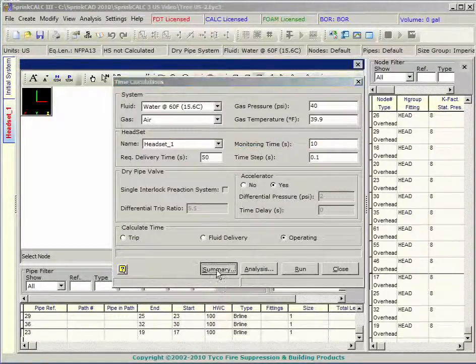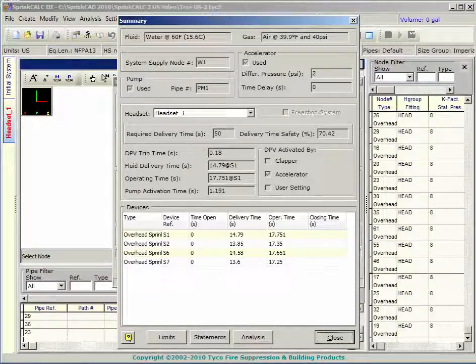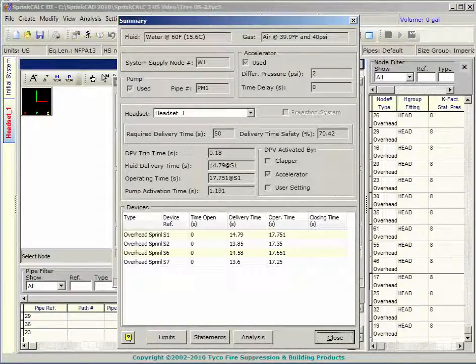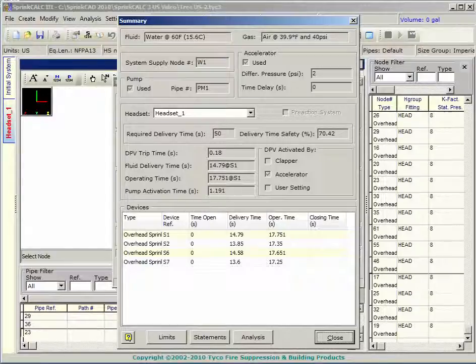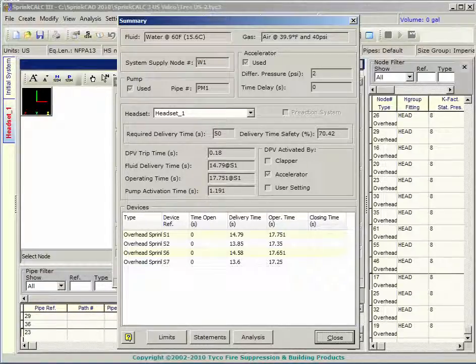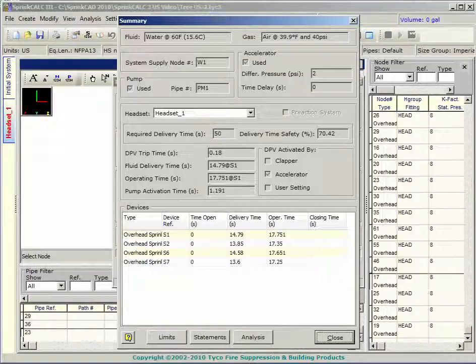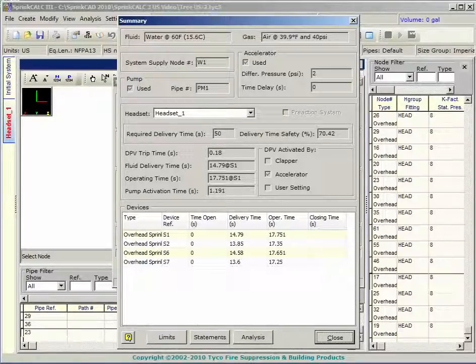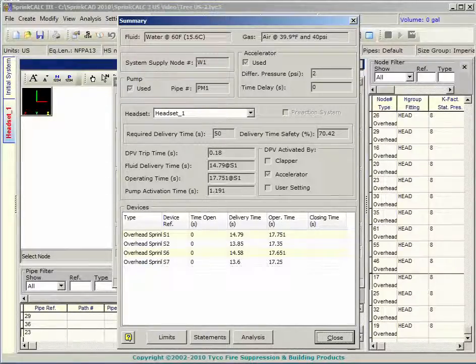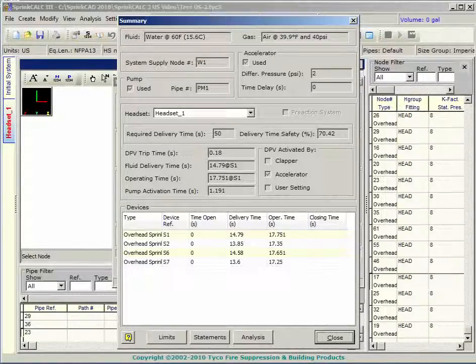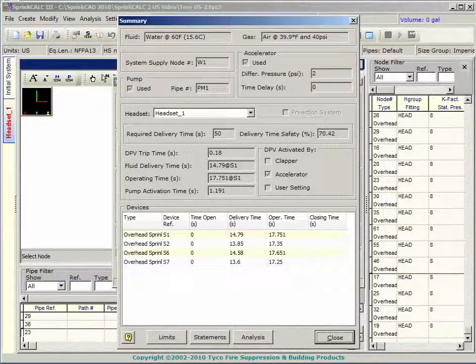The summary dialog box shows a snapshot of the results. The pre calc settings are shown at the top. Below this are the operating times for the dry pipe valve and the pump. The fluid delivery time and operating time are displayed for the most demanding heads. The table lists the delivery and operating times for all sprinklers in the headset.